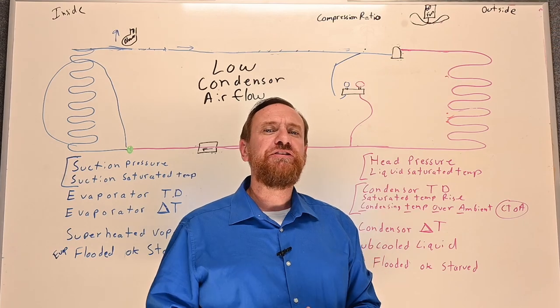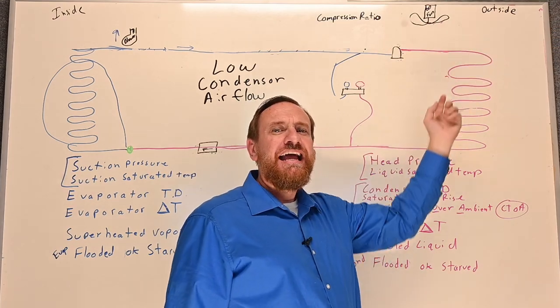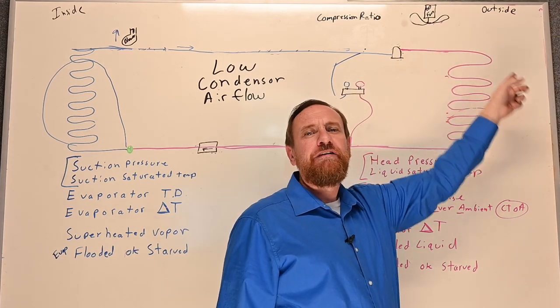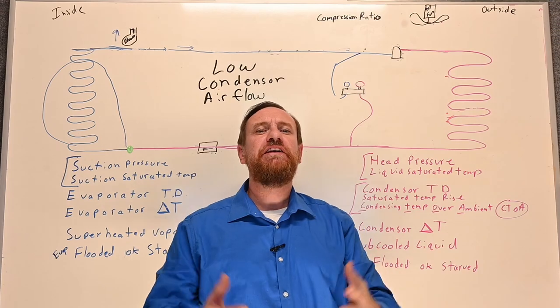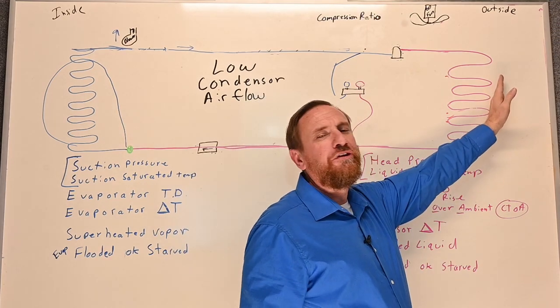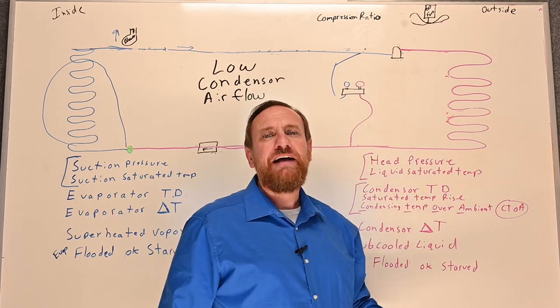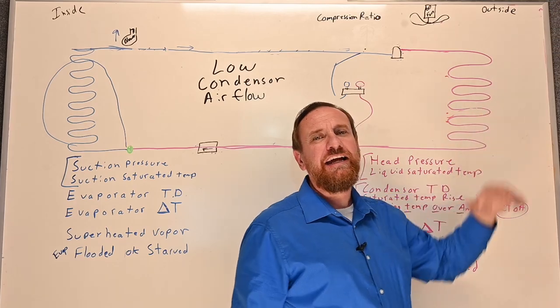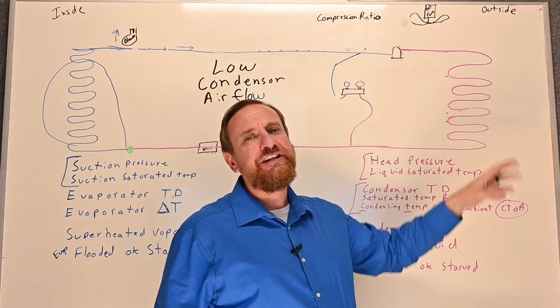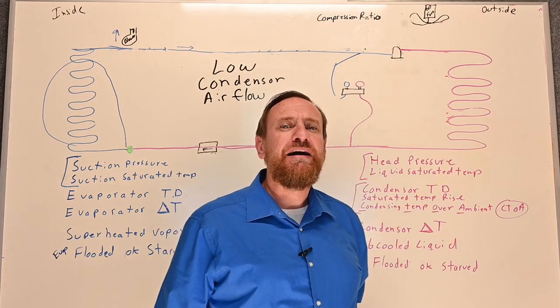Another cause related to airflow would be air recirculation. If somebody built something on top of the condensing unit, the air coming out would hit it and come back around — that's air recirculation. Yet another example is something too close to the condensing unit; maybe they placed it too close to the house or have something next to it blocking the airflow. Airflow inside is important, but airflow outside is very important as well.